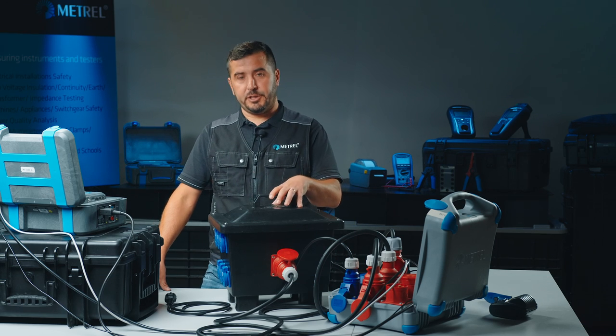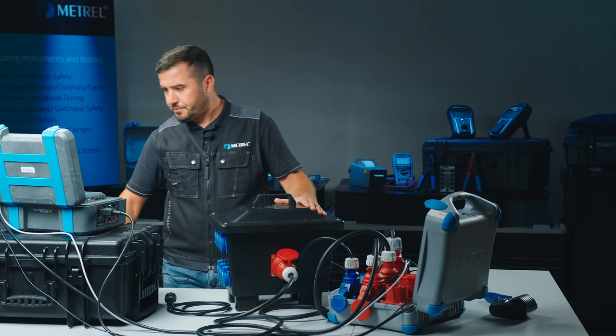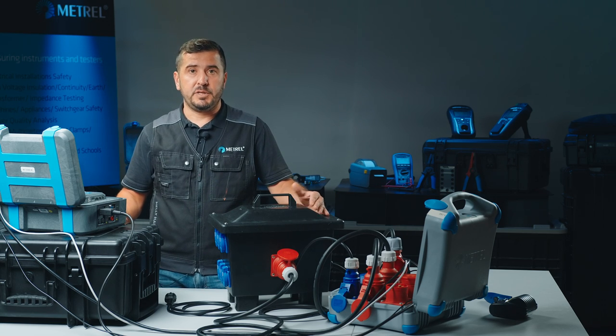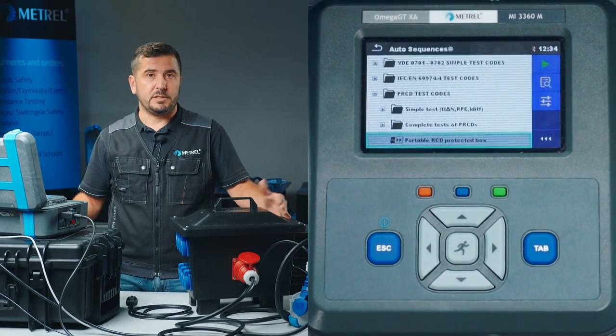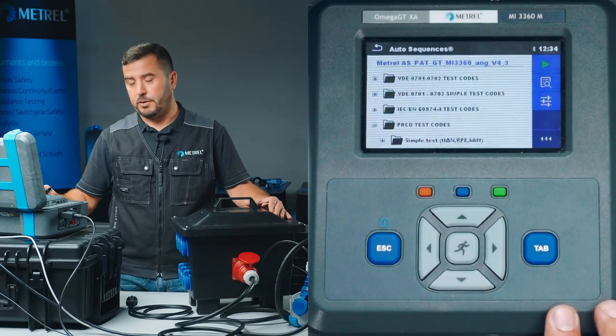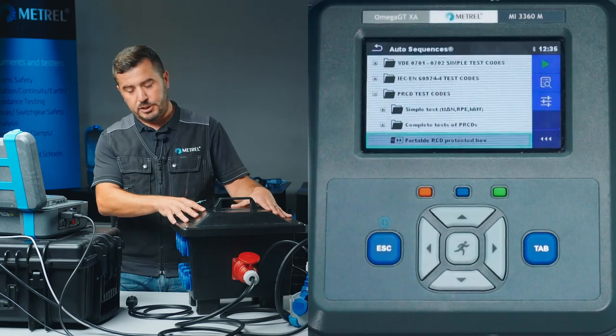For this application — testing of a portable RCD-protected box — I have created a special auto sequence dedicated for such equipment. The auto sequence was created with the help of ES Manager software, which is METREL's Electrical Safety Manager. It is suitable for printing test results and also for creation of auto sequences. Inside the group of default predefined test sequences, I have added a test sequence dedicated for testing of such equipment.